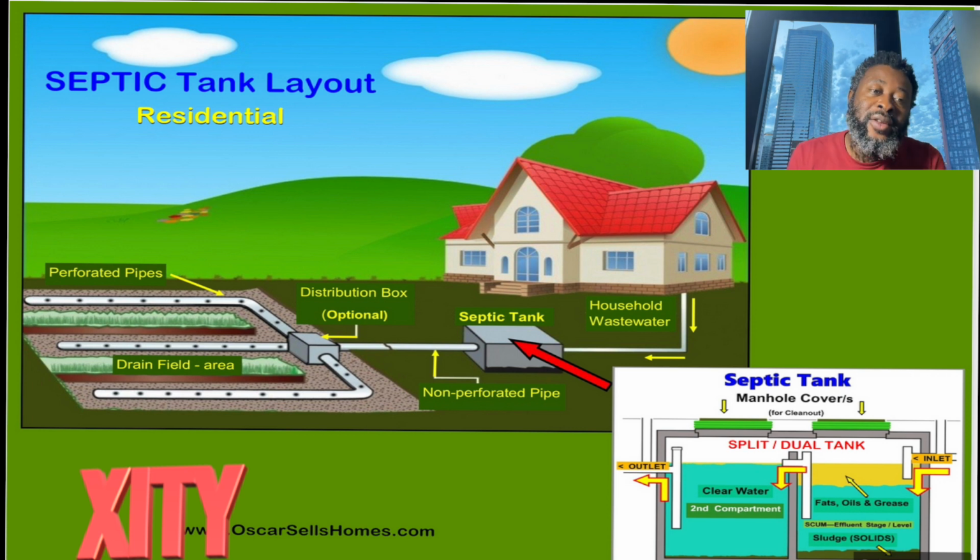But even when it is functioning normally, liquid going into the second vault may have some solid matter floating around in that liquid mixture, so some of that is gained over time. Once it is sitting in that second vault, after some time it tends to sink to the bottom. So you have a small amount of sludge in the second vault, but usually it's around a quarter of what you have in the first vault.